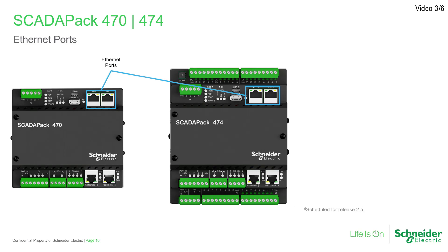The SCADAPack 47x RTUs have two Ethernet ports that support a number of useful features, including independent subnets that allow for separate and/or redundant Ethernet connections, enhanced cybersecurity with individually addressable Ethernet ports and IP and service port whitelisting, and a switch mode option that supports both ports on the same subnet.